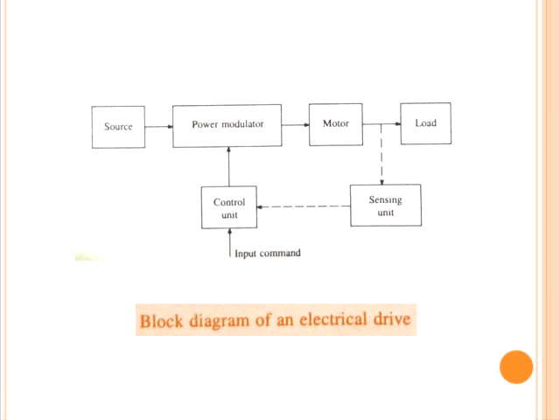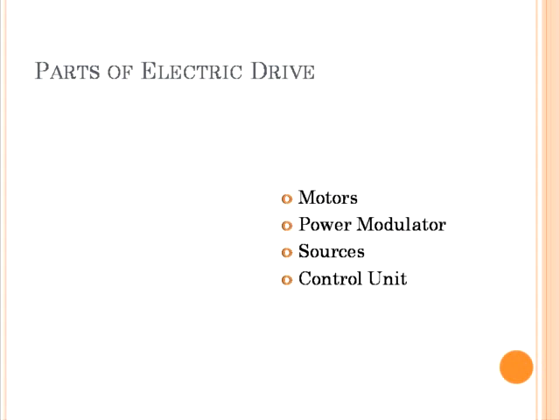In the past, induction and synchronous motors were employed mainly in constant-speed drives; variable-speed drives consisting of these machines were either too expensive or had very poor efficiency. Consequently variable-speed drive applications were dominated by DC drives. AC motors are now used in variable-speed drives due to the development of semiconductor converters employing thyristors, power transistors, IGBTs, and GTOs.